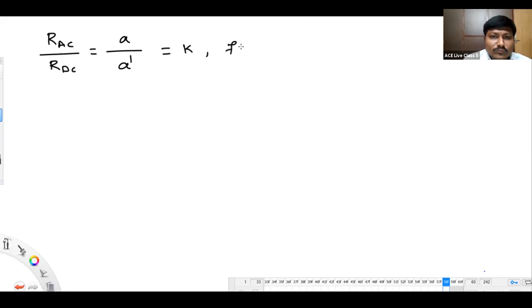Conductor resistance for AC supply will be equal to K into conductor resistance for DC supply. How is the value of K to be expected? Definitely greater than 1. As K is greater than 1, definitely the conductor is going to offer more resistance for AC supply compared to the DC supply.